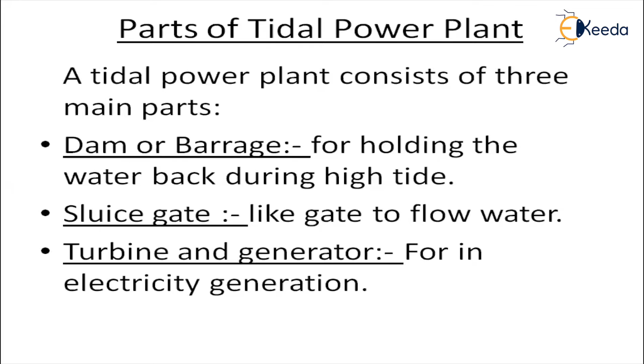So we see the parts in detail. First part, the function: create a barrier between the sea and the basin. Another important point is that a tidal power barrage has to resist the waves, whose shock can be severe, and even the pressure changes side continuously. So the barrage needs to provide a channel to the turbine in reinforced concrete. Location of the barrage is very important because the energy available is related to the size of the trapped basin and to the square of the tidal range. It is never built in the mouth of the bay, because the larger the basin, the smaller the tide range.